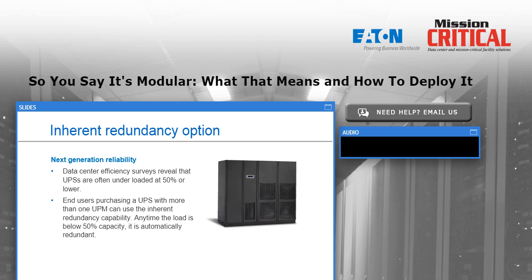If I had a larger system based on the same UPM model, let's say it has 3 of those UPMs, now my load level is 66%. As long as the load is less than 66%, then I can live without any one of those 3 power modules. So if I have a problem, if I need to do maintenance, I can disable or take the affected power module offline, and the UPS system can remain online. And in many parts of the world, that's exactly how we service it.